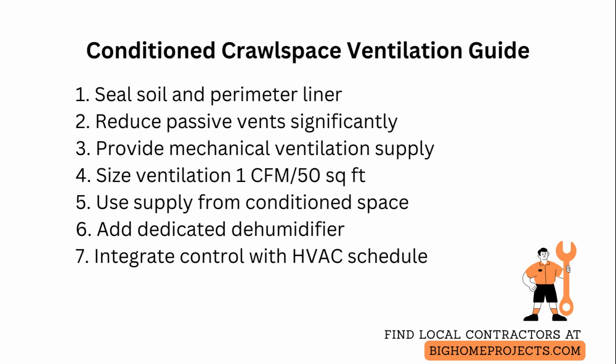Include a dedicated dehumidifier sized for the crawl space volume and local climate to maintain relative humidity below 60% and prevent mold and rot. Finally, integrate the crawl space ventilation control into the home mechanical schedule or thermostat so the system runs only when needed and does not overload the heating and cooling equipment.